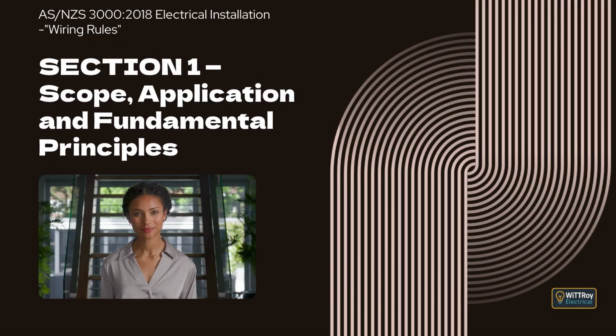Clause 1.5.4.2 Methods of protection. Basic protection can be achieved by one or more of the following methods. Method 1. Insulation. Covers live parts completely with electrical insulation that can withstand mechanical and environmental stresses, and the insulation must only be removable by destruction. Method 2. Barriers or enclosures. Live parts are placed behind barriers or inside enclosures that meet certain degrees of protection, such as IP2X, IP2XB, or IP4X for horizontal surfaces. The idea is simple: you should not be able to touch live parts unintentionally.